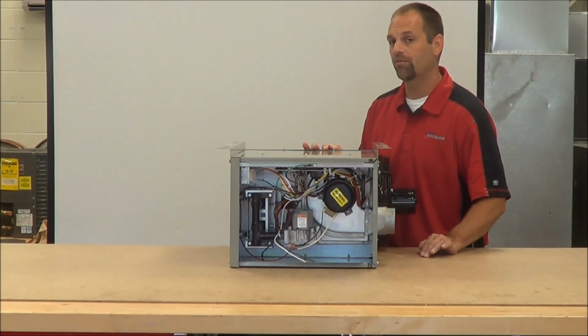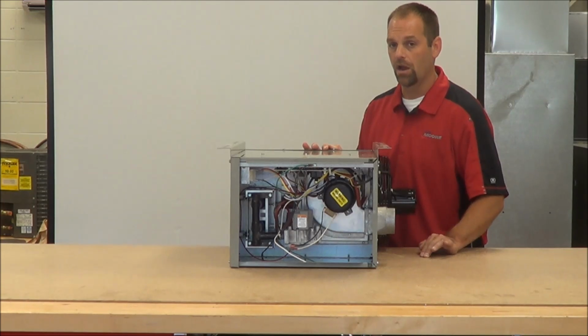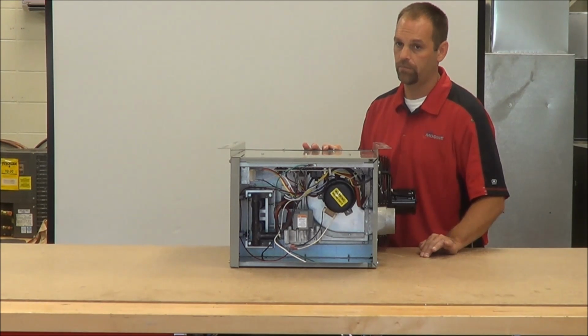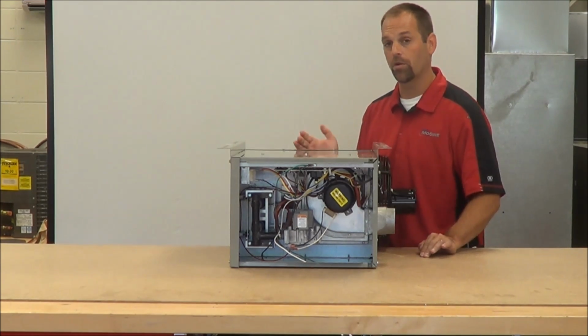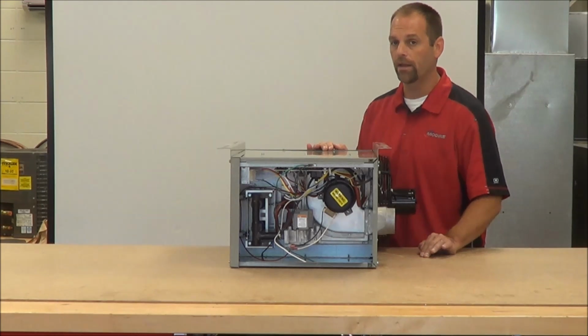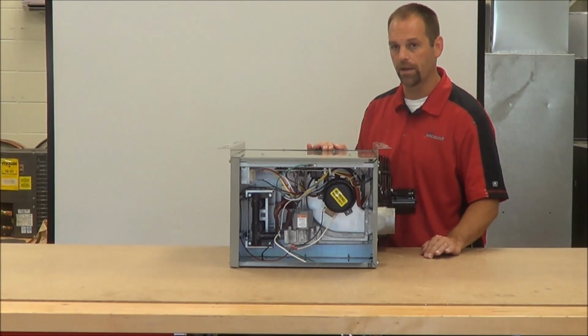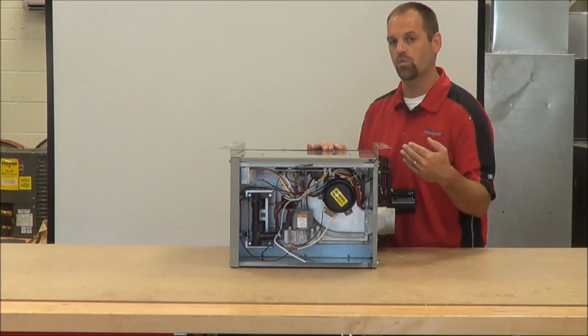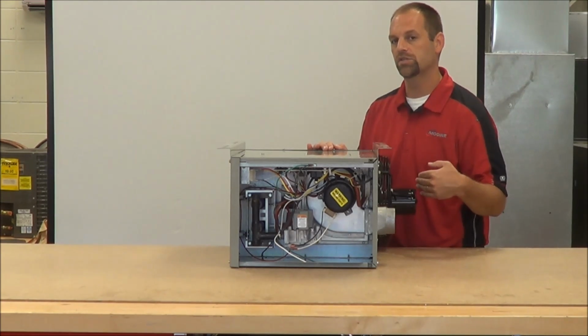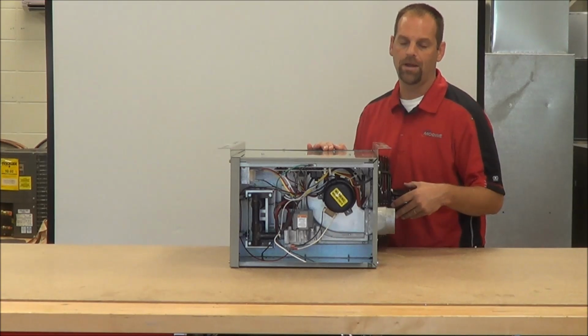or the wires that are run from the thermostat to the unit are exceeding what they should be. A lot of times people will run the thermostats 100 feet away, or I should say 50 feet away, and that's too long for the size wire they put in there. And what it'll do is it'll increase the amp draw and it'll pop that secondary.